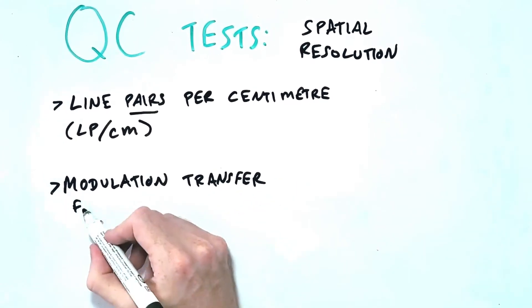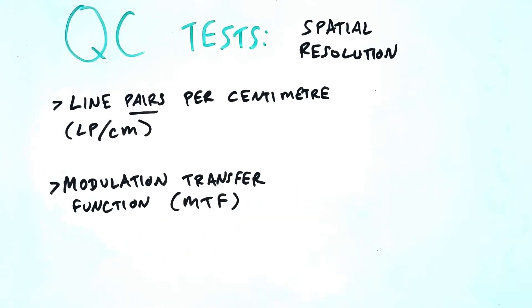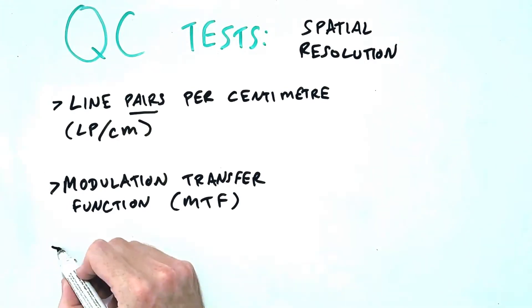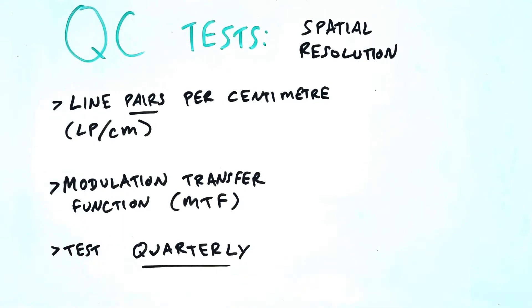Besides assessing spatial resolution with this phantom, we can also use the modulation transfer function, or MTF, which is a mathematical description of the spatial resolution limits of the scanner. Spatial resolution should be tested quarterly.